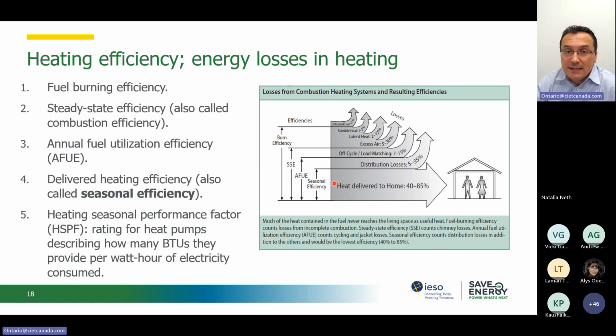For high efficiency boilers, that may be around 85% efficiency. So we still see that we get this type of, I guess, opportunity if we address some of the losses here. If we reach that 85%, there is not much more we can do. So that's where we are going to look into alternative solutions for heating and cooling in our buildings. And one of the topics that we are going to cover will be heat pumps, very trendy now in discussion for retrofits related to heating systems.